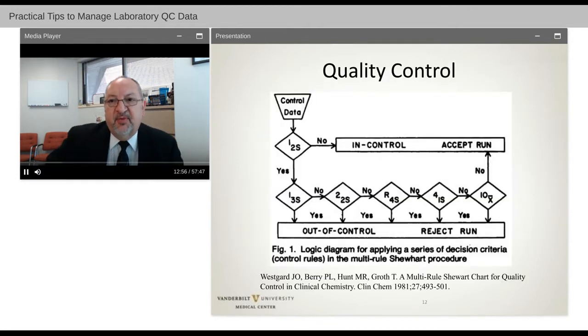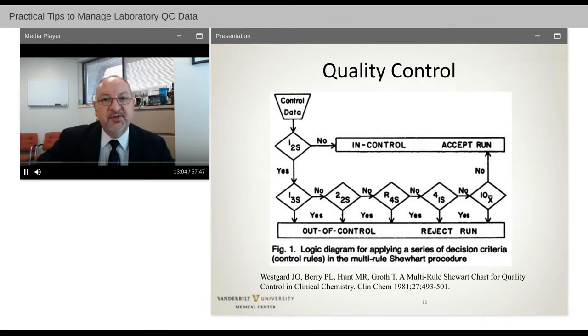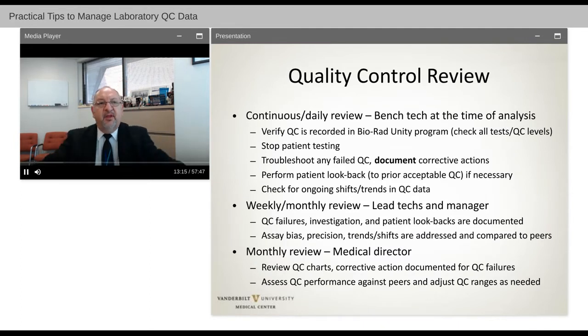You may be familiar with Westgard's chart for troubleshooting and determining whether quality control is in range or out of range, and whether it is acceptable to continue to release results or to stop testing and troubleshoot. Now, it's important that we look at our quality control data continuously as we run quality control, whether it be periodically every so many hours, or so many patients on a continuous run, every 20, 50, 100 patients, depending on the performance of that assay.